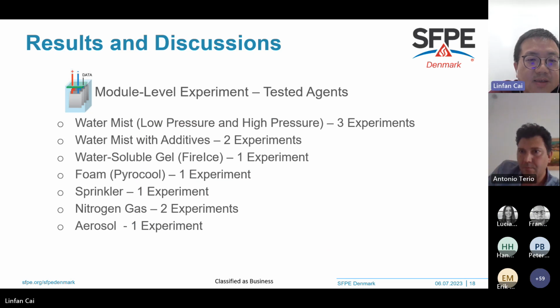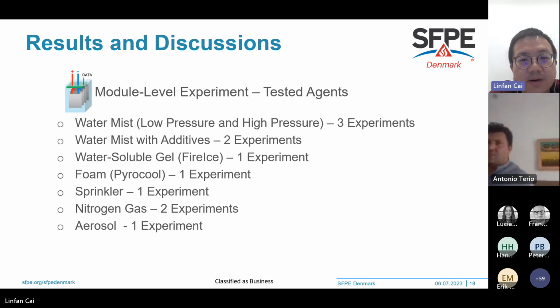These are the tested agents for the module level experiment. The two with the highest performance are high pressure and low pressure water mist, and water mist with additive. Other experiments used FireIce, foam, sprinkler systems, nitrogen, and aerosol.